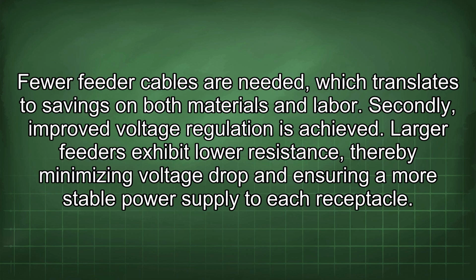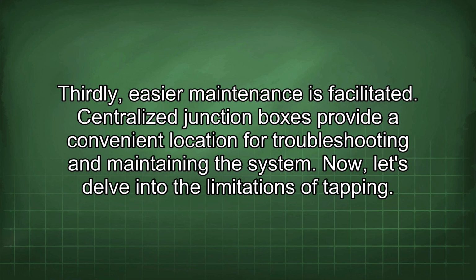Secondly, improved voltage regulation is achieved. Larger feeders exhibit lower resistance, thereby minimizing voltage drop and ensuring a more stable power supply to each receptacle. Thirdly, easier maintenance is facilitated. Centralized junction boxes provide a convenient location for troubleshooting and maintaining the system. Now let's delve into the limitations of tapping.